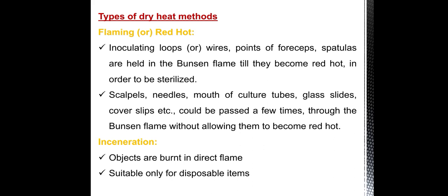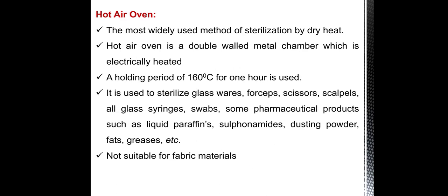Incineration: objects are burned in direct flame, suitable only for disposable items. Hot air oven: the most widely used method of sterilization by dry heat. Hot air oven is a double-walled metal chamber that is electrically heated. A holding period of 160 degree Celsius for 1 hour is used. It is used to sterilize glasses, forceps, scissors, all glass wares, swabs, some pharmaceutical products such as liquid paraffins, dusting powder, fats, etc. Not suitable for fabric materials.